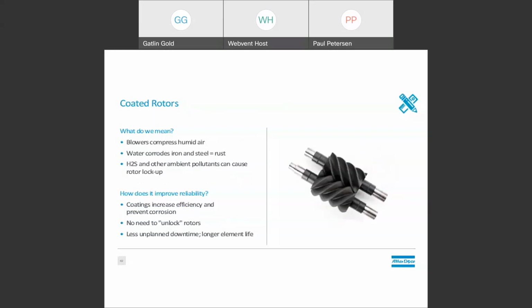Blowers compress ambient air. So even in dry desert conditions, there is some humidity present. During normal operation, water particles are passed downstream into the basin, right? We're not like in high pressure compressor applications, forming condensate while the blower is running. Typically, it all goes downstream. But once the blower stops, condensation begins to form on the rotors inside the compression chamber. Well, water corrodes iron and steel, which are the most common rotor materials. It's extremely common to see rust formations on uncoated rotors within a year or a few short years of operation.